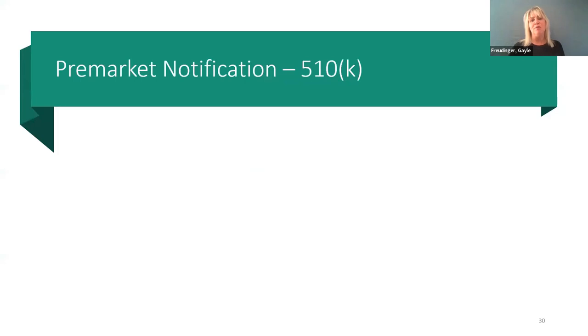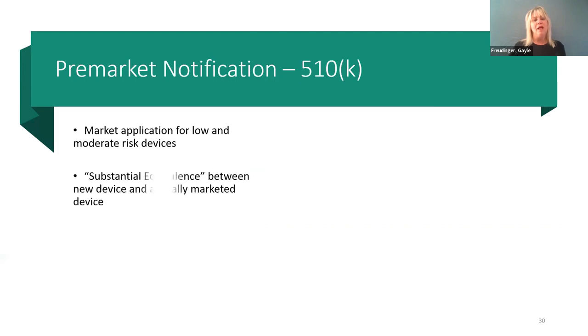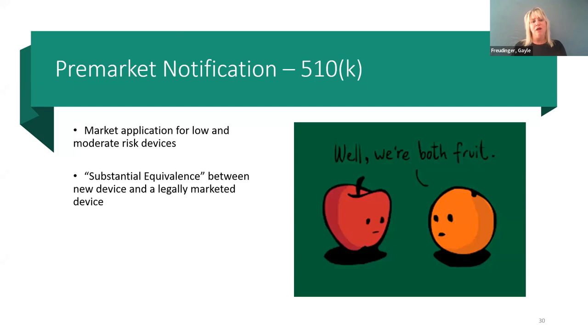The 510K is probably one of the most popular pre-market applications. And this is for low and moderate risk devices. It's often required for class one and mostly for class two devices. It's made to the FDA. The purpose here is to demonstrate that your device to be marketed is safe and effective, and that it's substantially equivalent to a legally marketed device that's already out there. This involves a demonstration of the new device, and you're going to compare it to the existing device. You're going to look at intended use, the technological characteristics and what's similar and what's different, where there might be concerns in safety and effectiveness, and what types of performance testing you've done.